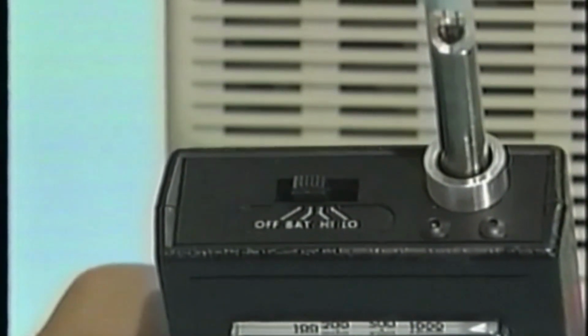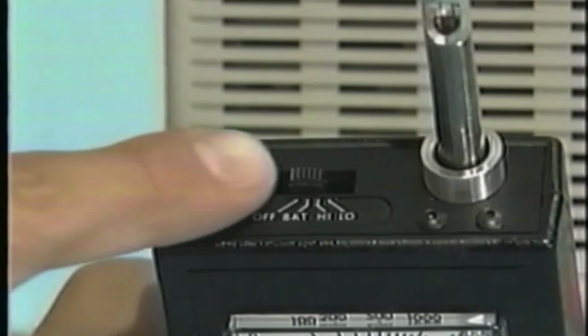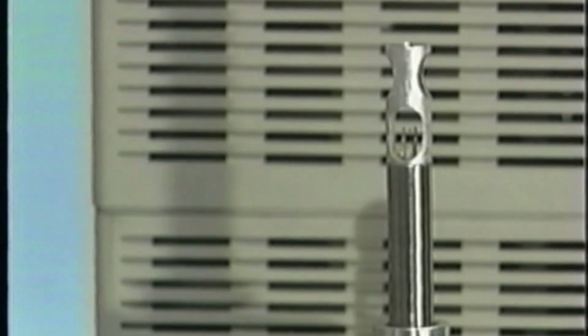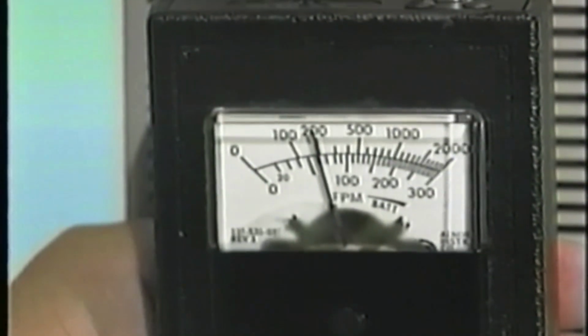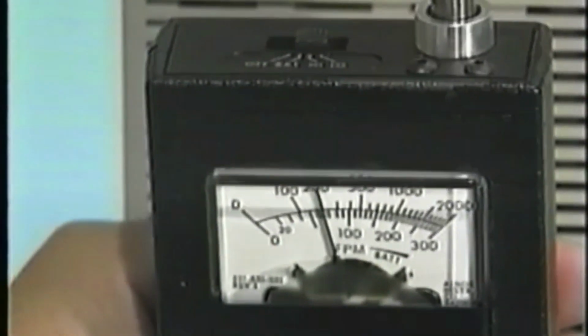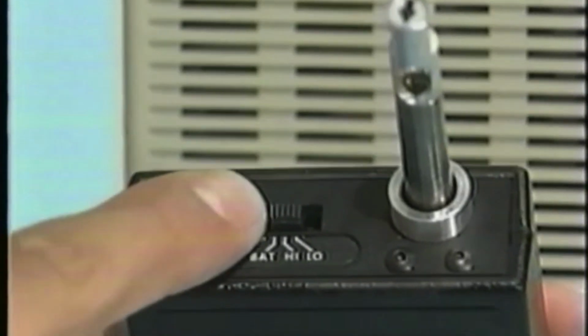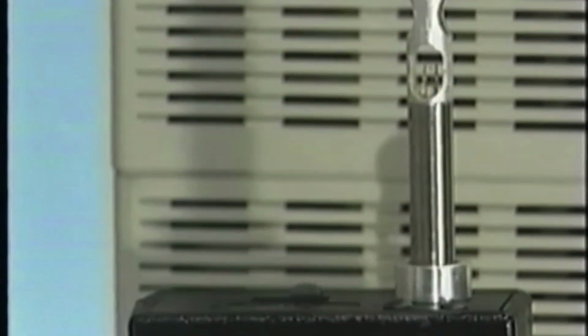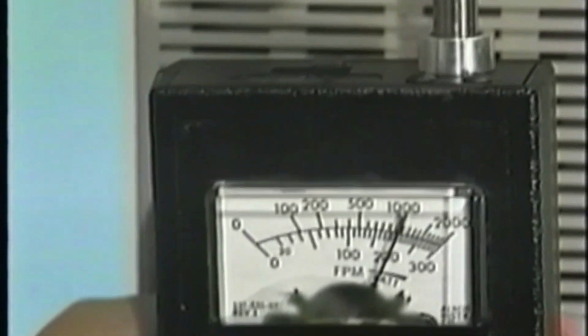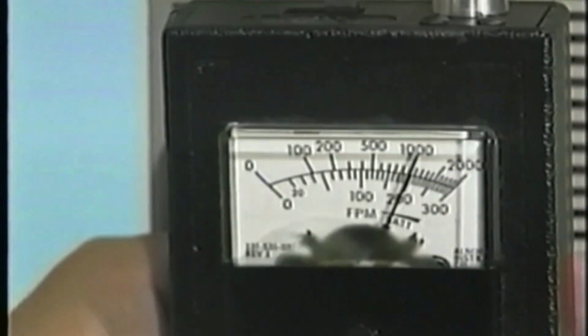To measure the airflow, slide the switch at the top of the instrument to the high position and place the instrument in the airflow. Check the velocity reading on the meter. If the velocity is below 250 feet per minute, move the switch on the top of the instrument to the low position for better resolution. The operational temperature range of 32 to 122 degrees Fahrenheit should not be exceeded.